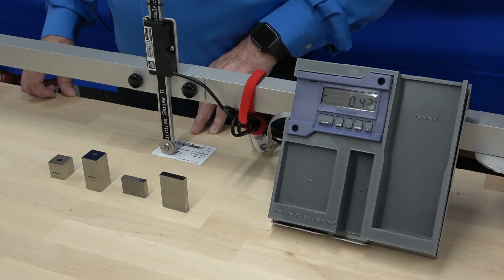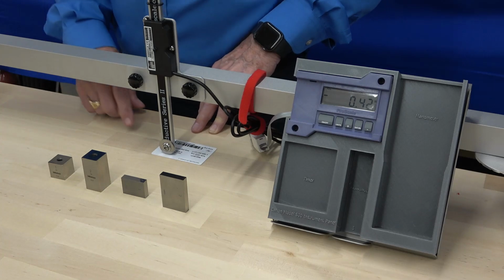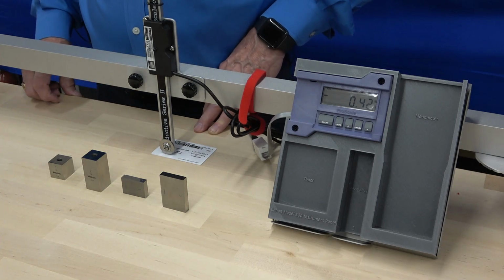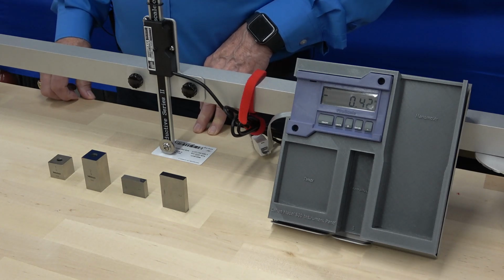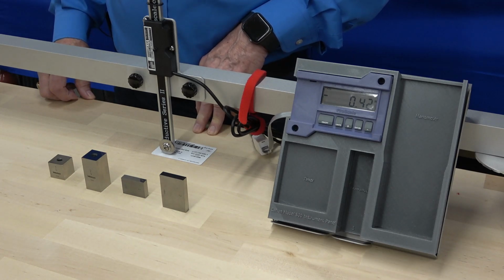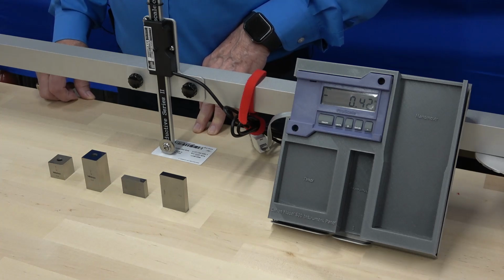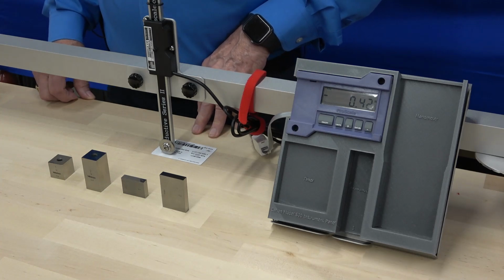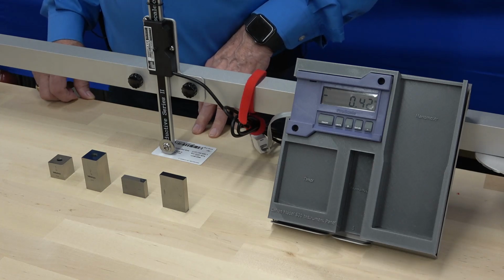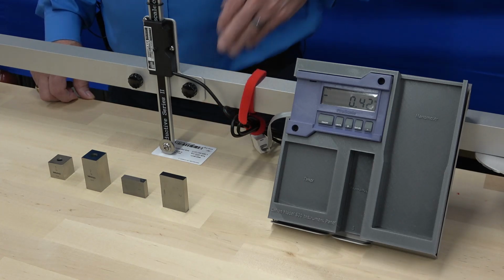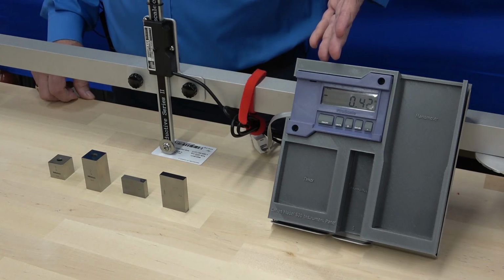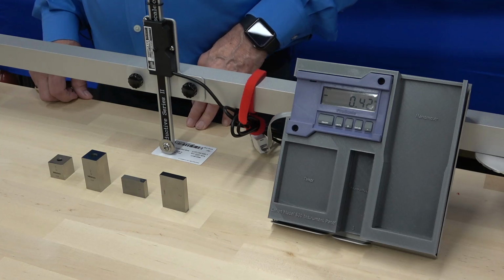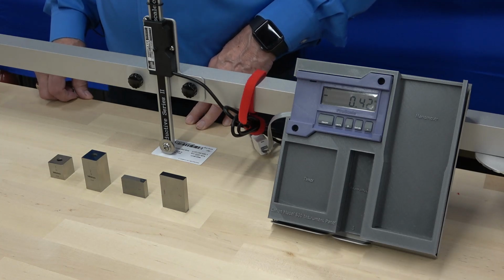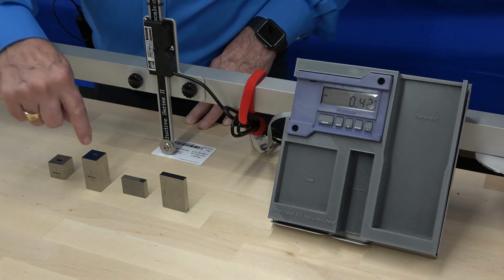If you're using a credit card, make sure that the foot is not on top of one of the embossed numerals or letters. This particular card is smooth surface, so I don't have that concern. So to run the test, you will need a set of calibration blocks. These are machined to a very high tolerance of 1/1000th of an inch or better. The device reads to the nearest 100th of an inch, so 1/1000th of an inch calibration block will be fine. You'll need a 1 inch and a 2 inch.